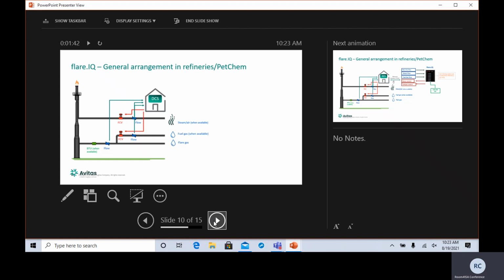There's something most plants refer to as your steam to vent gas ratio. Most places it's a standard 1 to 1: for every pound of flare gas you go through, put a pound of steam into your line. It's great most of the time until you have a process upset where your molecular weight changes and you get a bunch of black smoke. Then you start cranking up the steam, which means you have to crank up the fuel gas. All in all, it's not an optimal situation.